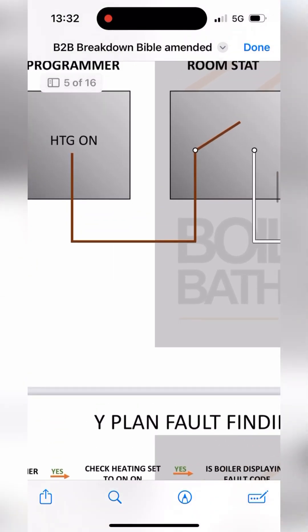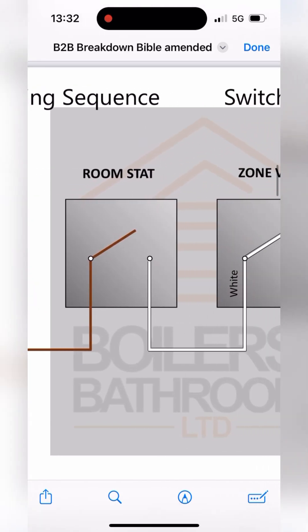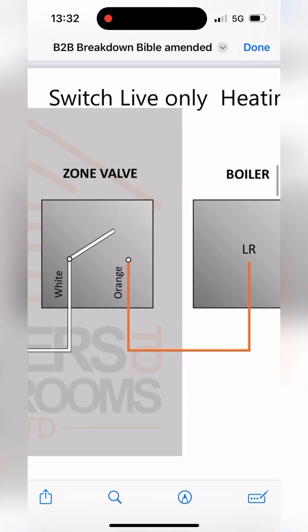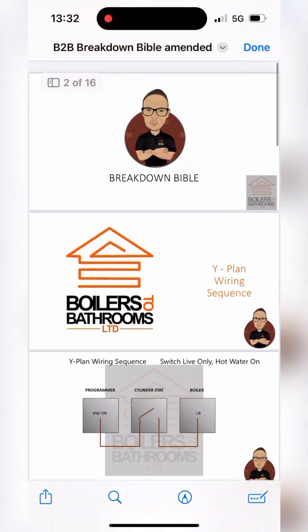If we scroll up, we go to Y plan wiring sequence: heating on goes from the programmer to the room stat, and then from the room stat to the zone valve on white, makes the switch over to orange to fire the boiler. It wasn't firing the boiler, so that's how we identified the zone valve.